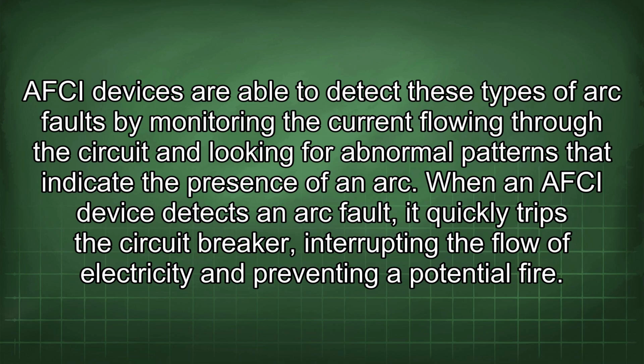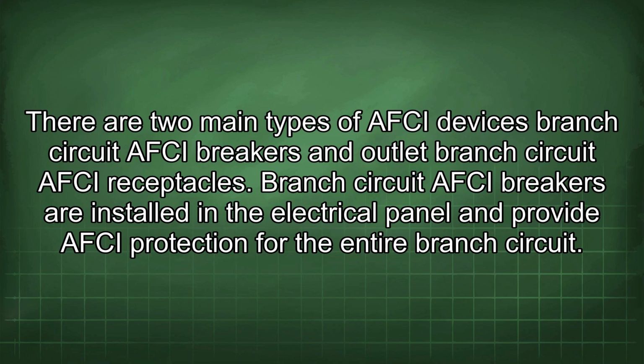When an AFCI device detects an arc fault, it quickly trips the circuit breaker, interrupting the flow of electricity and preventing a potential fire. There are two main types of AFCI devices: branch circuit AFCI breakers and outlet branch circuit AFCI receptacles. Branch circuit AFCI breakers are installed in the electrical panel and provide AFCI protection for the entire branch circuit.